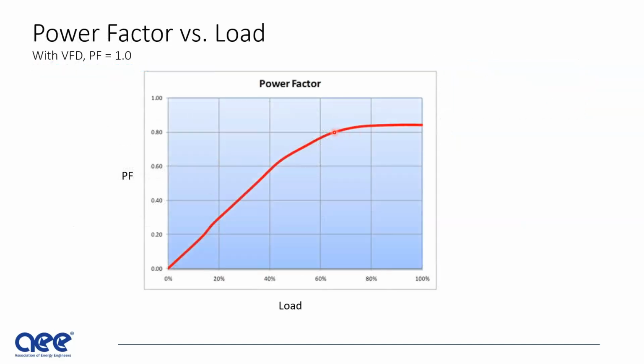Power factor, as you see, once you get below 60%, really drops off. And I've been in factories where power factor was 28% or 22%, and it's because invariably they have a lot of large motors that are lightly loaded. They didn't realize that when they changed their processes to not need as much horsepower, they should have changed the motor as well.